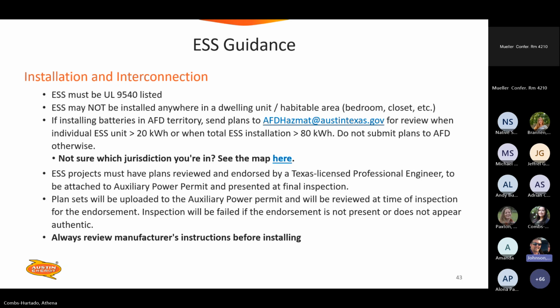An ESS project must have plans reviewed and endorsed by a Texas licensed professional engineer and be attached to the auxiliary permit and presented at final inspection. We do need the drawings on site. It can be digital, it can be in paper form, either one. We just want to make sure that what was approved by the PE was what was installed, which is what the customer is getting. Plan sets will be uploaded to the auxiliary power permit and will be reviewed at time of inspection for endorsement. Inspection will be failed if the endorsement is not present or does not appear authentic. If it's blurred, if it's not real, if someone just signed off on it, it has to be an actual PE for energy storage system projects.